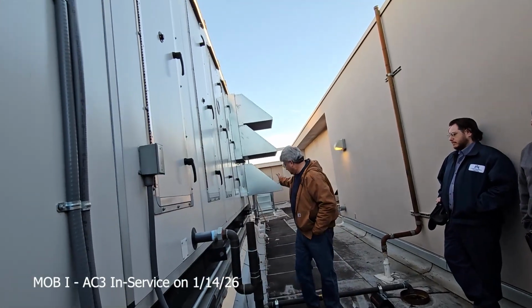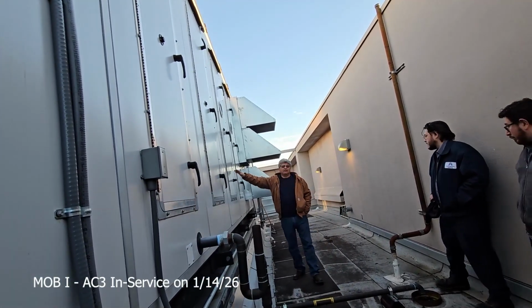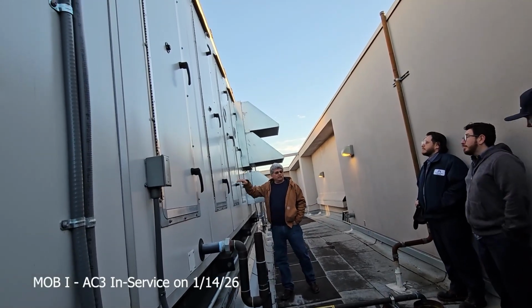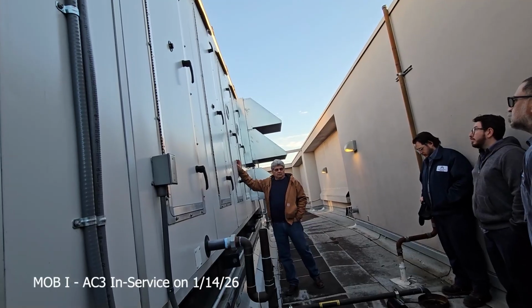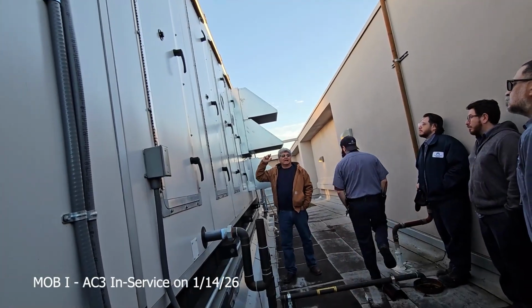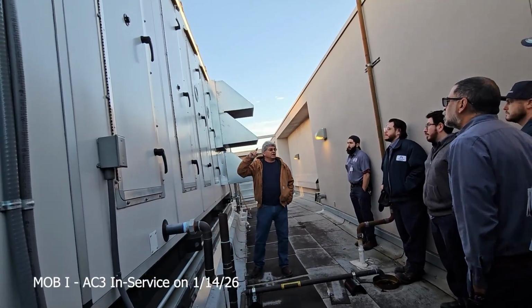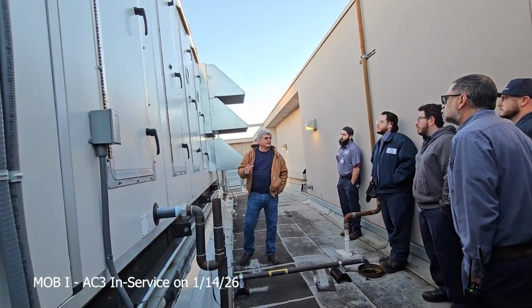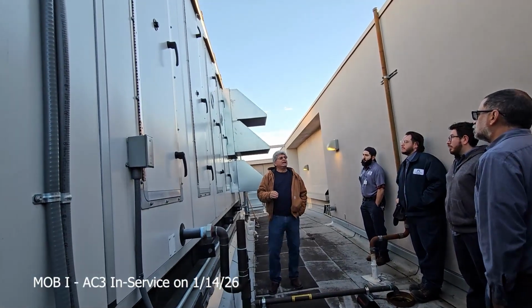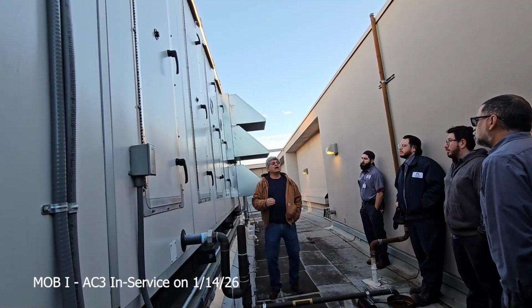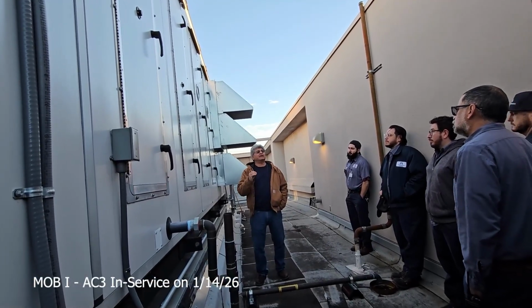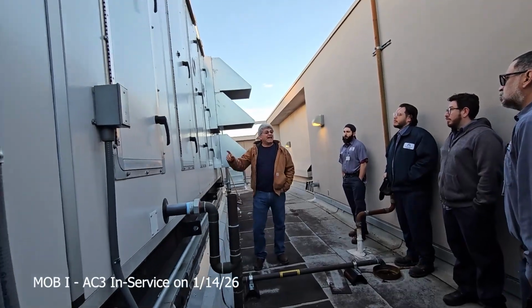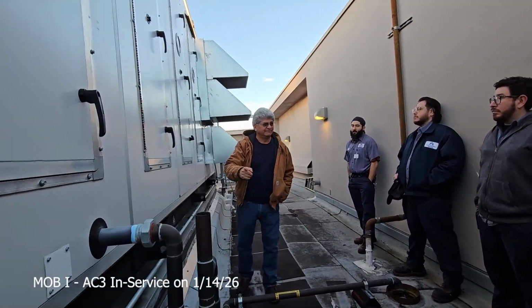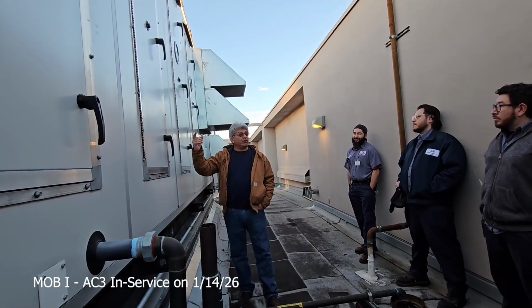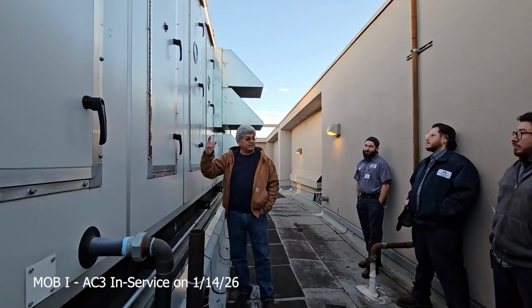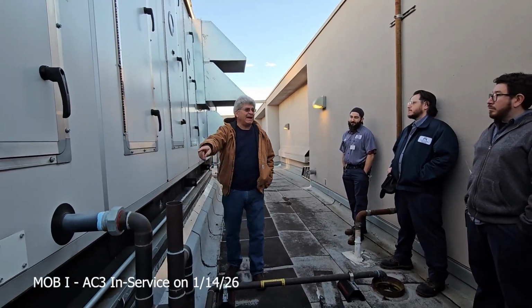Watch out here. In this compartment here, your filters, you've got 2 sets. If they go too long, these supply fans and return fans are strong and powerful. They don't care if your filters are dirty. They're still going to want to give you the same static, the same CFM. So they will pull the dirt off of your filters. And then that dirt collects on your evaporator coil. When in the summertime the evaporator coil gets nice and wet and it's condensing, all that dirt goes into your pan.